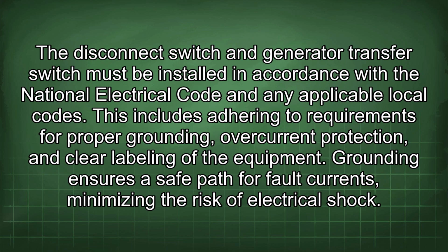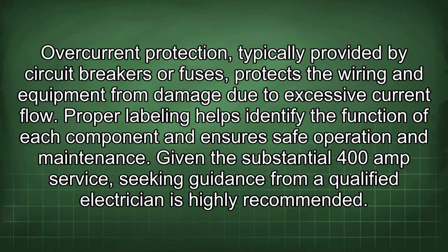The disconnect switch and generator transfer switch must be installed in accordance with the National Electrical Code and any applicable local codes. This includes adhering to requirements for proper grounding, overcurrent protection, and clear labeling of the equipment. Grounding ensures a safe path for fault current, minimizing the risk of electrical shock. Overcurrent protection, typically provided by circuit breakers or fuses, protects the wiring and equipment from damage due to excessive current flow. Proper labeling helps identify the function of each component and ensures safe operation and maintenance.